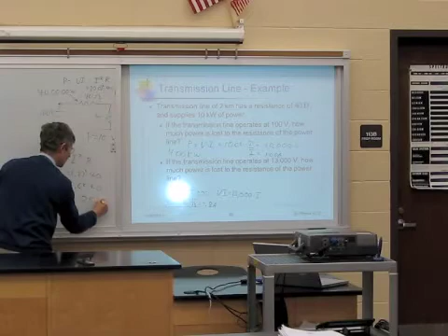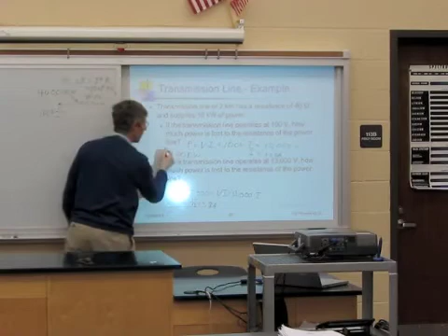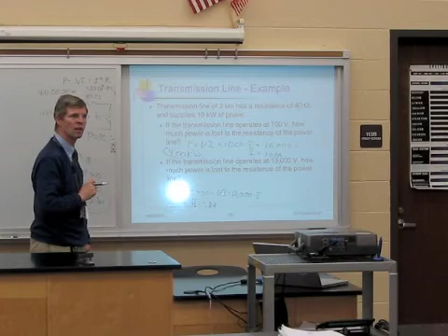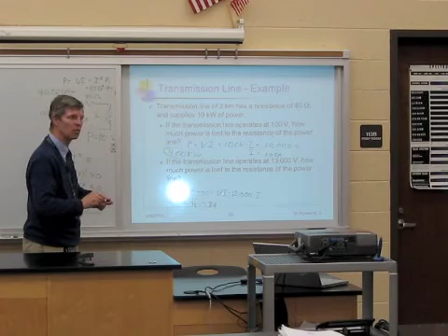How much power would we dissipate in this 40 ohms of resistance for this transmission line? Using I squared R, that's roughly 0.8 squared times 40. 0.8 squared is about 0.64, times 40, so that's somewhere around 24 to 25 watts. So the savings: operating at high voltage, we dissipate about 25 watts, compared to 400,000 watts at the lower voltage. That's really why people use high voltage power lines — for the same resistance, you don't lose nearly as much to resistive power losses as you do at lower voltages.